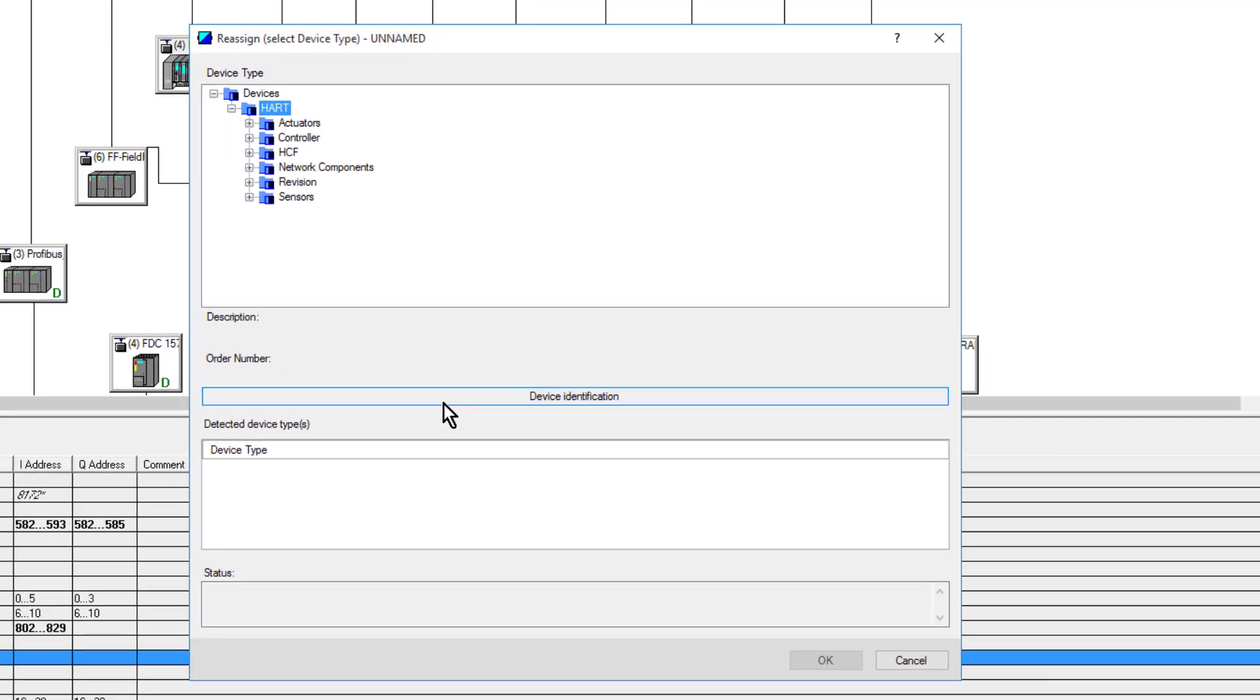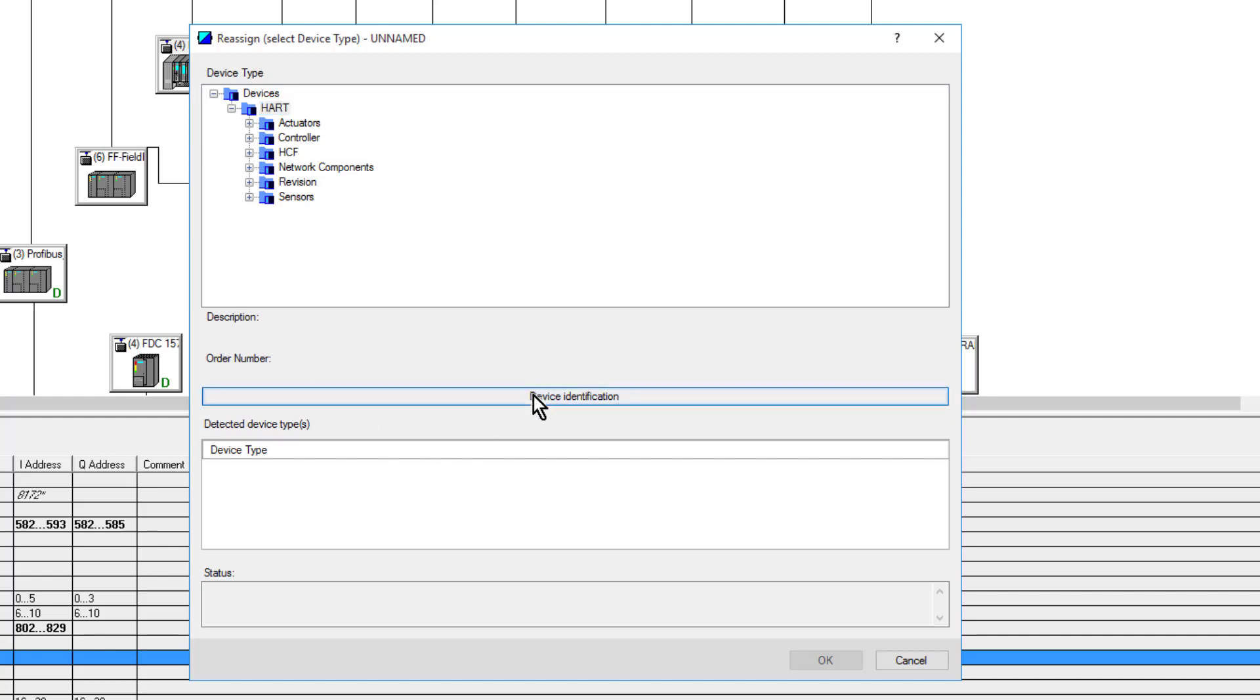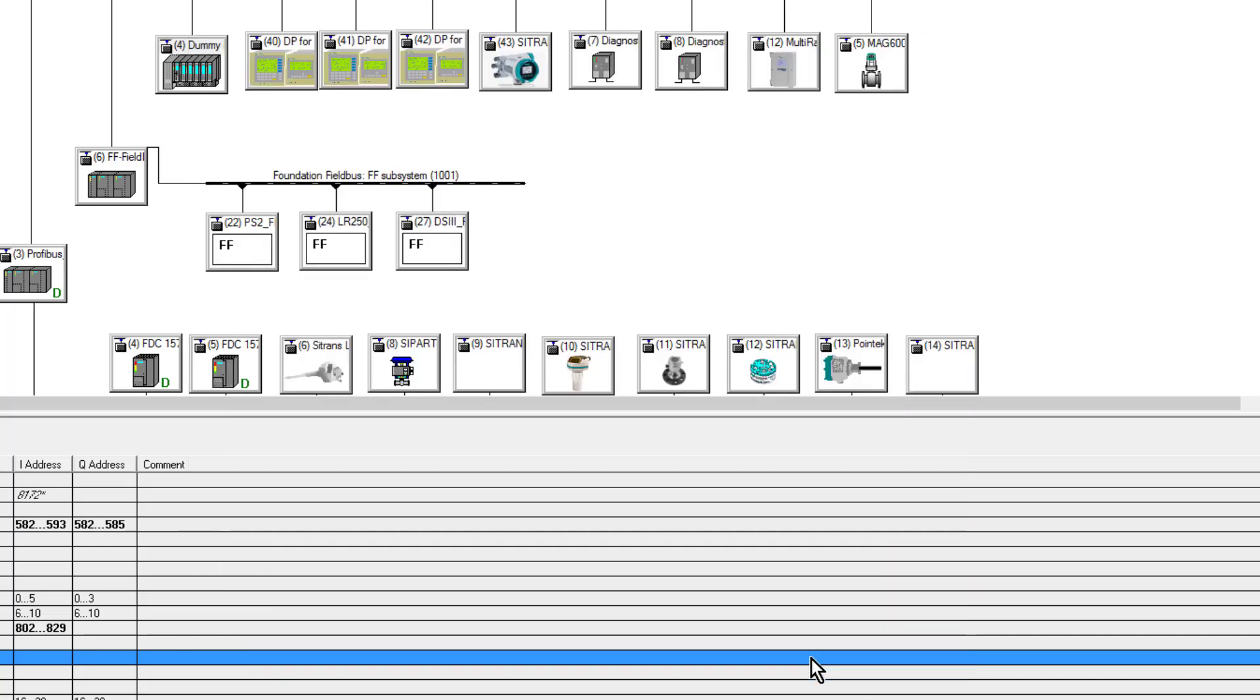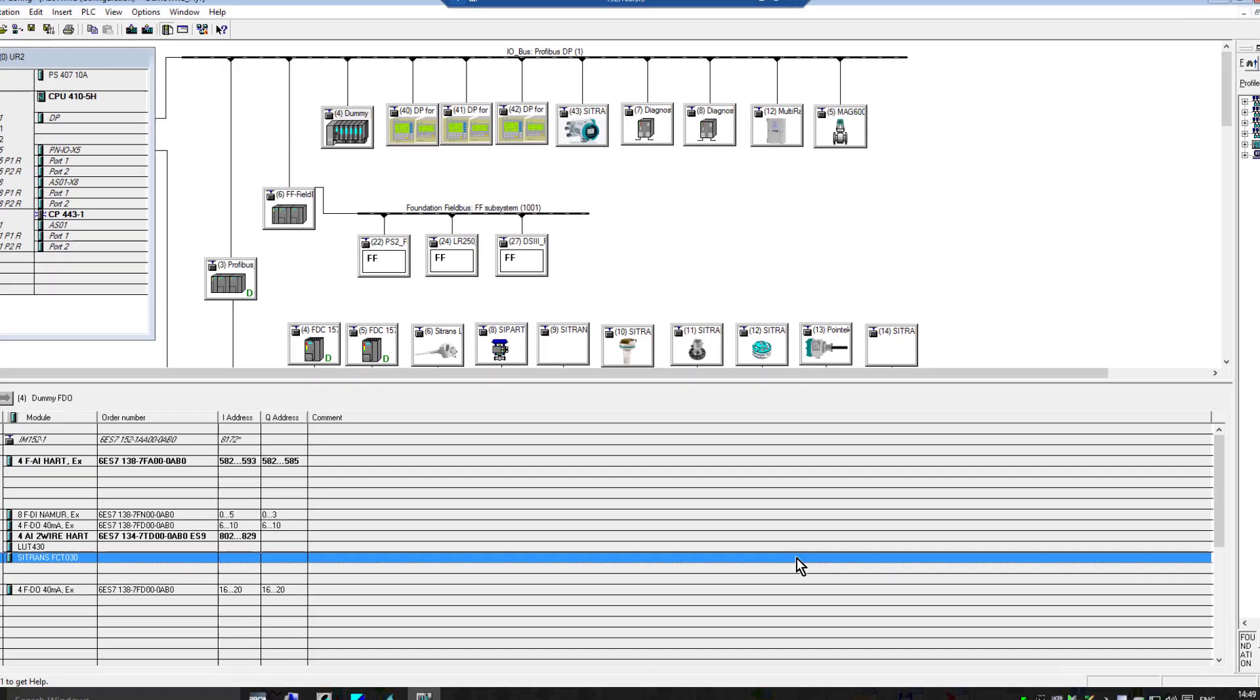If I double-click this name, it will try to open up PDM, but it still doesn't know what the device is. The card is not a HART multiplexer. All devices connected need the default HART address set to zero—that's what they'll be set to from factory. If you change the HART address to anything else, it won't communicate with this card. All we need to do is click on device identification. Revision 4—it's found the correct revision.